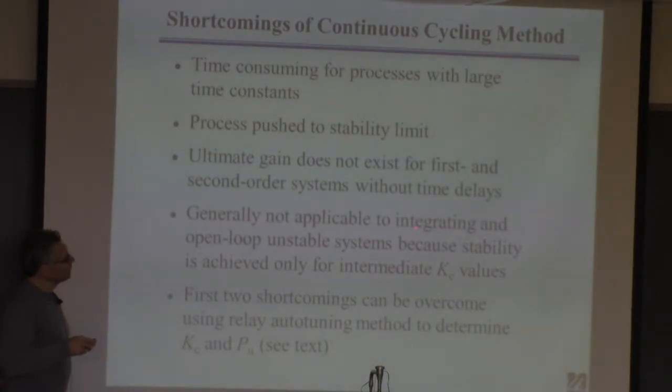You're not going to be able to do this if the system is integrating. Remember, integrating is like a tank, like a storage tank for fluid. It holds inventory. Or if the system is open loop unstable, it means the process itself is unstable. Because in this case, stability is only achieved for intermediate values. So if the value is too high or too low, it doesn't work. It's hard to apply here because you'll have a lot of trouble finding that value.